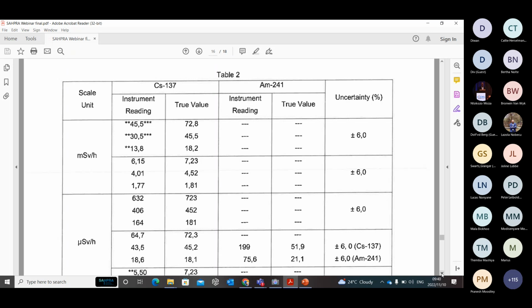And as well, on your right-hand side, you see that you have your uncertainty. As I mentioned earlier, no measurement result is complete without uncertainty associated with it. What it means is that the measurement value that your instrument read is within a range. You can read from 45.5 minus 6% of that, and also add 6%, so there is a range from the minus to the positive. That gives you a range that says your instrument is okay or works perfectly at this range.